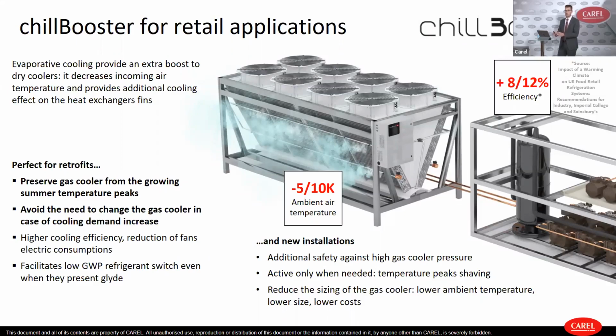You just need to put the adiabatic system and be prepared for the temperature peaks that will come. At the same time, this device is also good for new installation because by adding the Chill Booster, you don't need to size the gas cooler for temperatures like, I don't know, 40 to 45 degrees that are maybe happening just 1, 2, 3 times per year. So with the Chill Booster, you are keeping in safety conditions your gas cooler, your rack from these high temperature conditions that are becoming more frequent in these years.